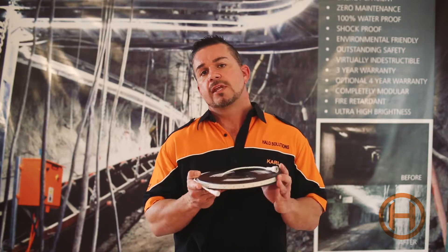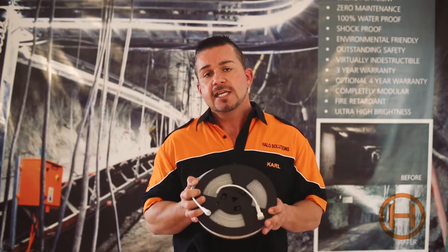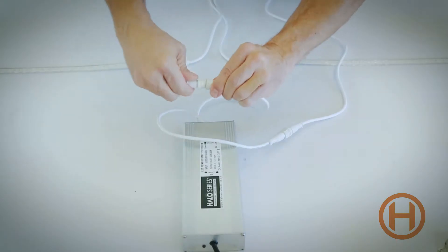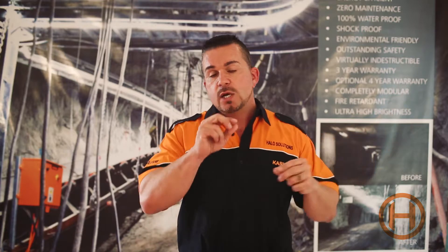The Halo 2 is the improved version of the traditional first generation product. These lights come complete with male and female adapters in 10-meter rolls, allowing quick and easy plug-and-play configuration. The lighting is connected to LED power controllers that provide protection and convert AC to DC voltage. The effective range of the Halo 2 fed from one side only is 20 meters. This range can be doubled by placing a power controller on each end, where one power controller powers the beginning of one solution and energizes the end of another — and with this piggyback configuration, lighting runs can extend indefinitely.